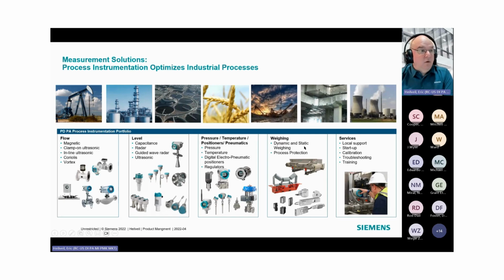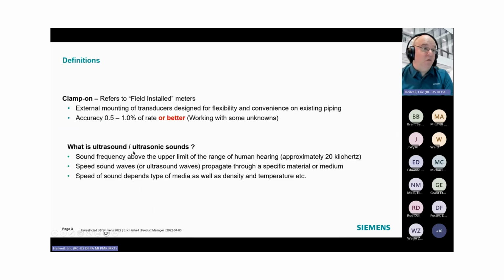There we go. So our clamp-on ultrasonic is part of a much larger process instrumentation offering that Siemens offers that FLW supplies to their regions. We do flow, of which clamp is part of. We measure level with both ultrasonic and radar, as well as guided wave radar. We do valve positioners. We measure temperature. We do pressure. We do dynamic weighing for solids, such as weigh feeders and scales and mass balances, and load cells, and of course offering a slew of services that FLW helps us supply to our customers. So our process instrumentation, the flow stuff, is just part of what we do.